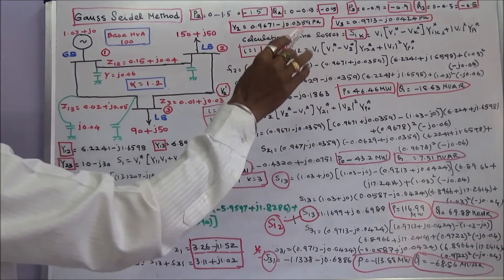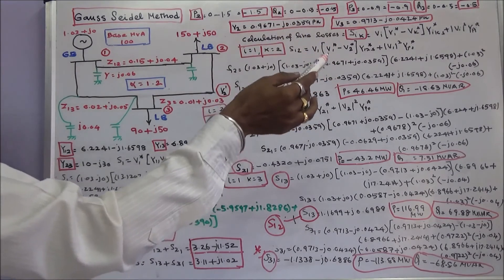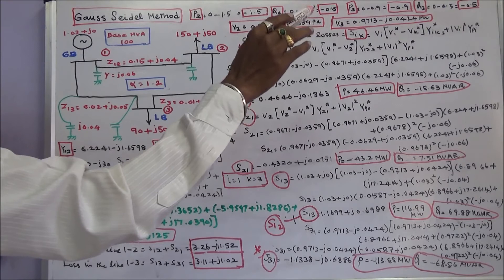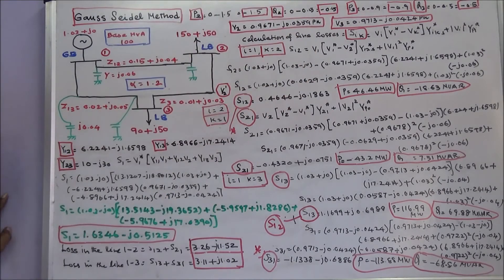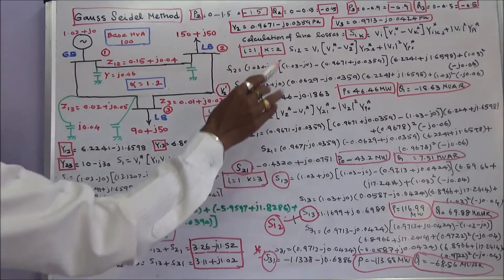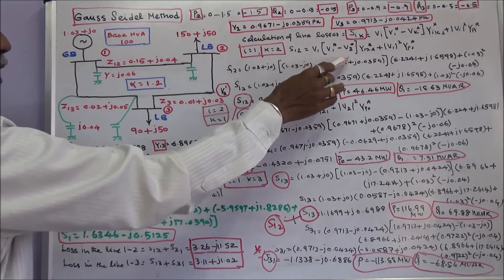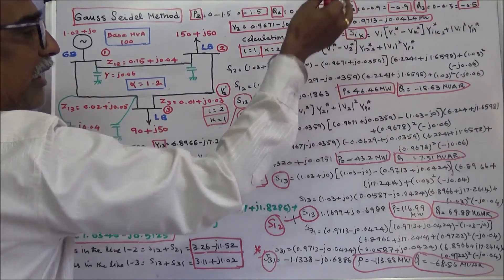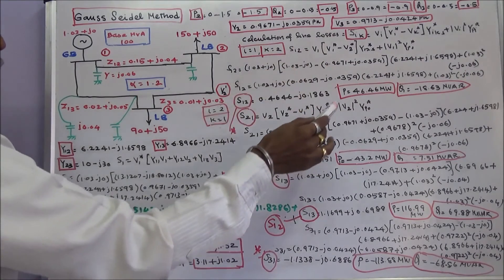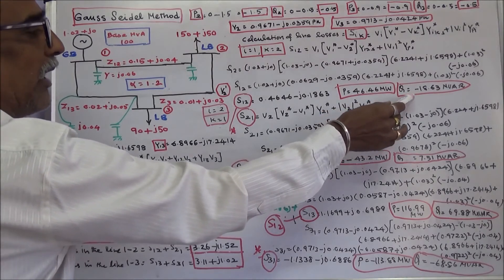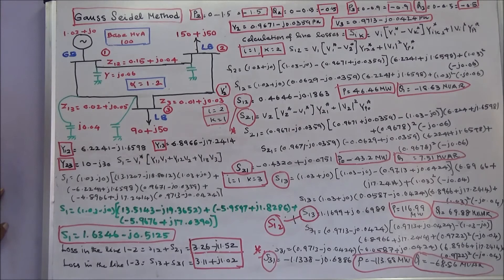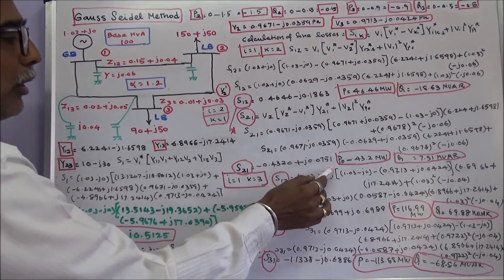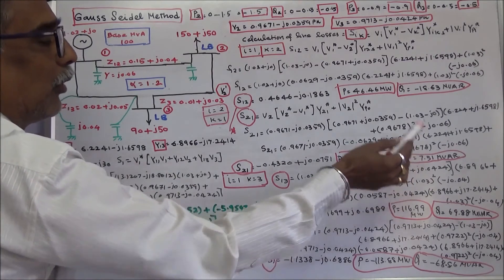The general formula is S_ik = V_i × [(V_i* − V_k*) × Y_ik* (series admittance conjugate)] + |V_i|² × Y_Pi* (half-line charging admittance conjugate). For S12 (I=1, K=2): P = 46.46 MW, Q = minus 18.63 MVAR. For S21 (I=2, K=1): P = minus 43.2 MW, Q = 7.51 MVAR.